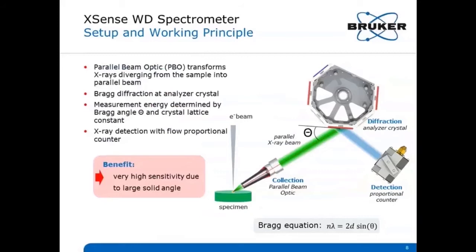This slide here shows the setup and working principle of the XSense spectrometer. The parallel beam optic is positioned very close to the sample, and thus captures a large effective solid angle. The optic, which is a very important part of this parallel beam spectrometer, is close to the sample, so we capture X-rays with a high effective solid angle.